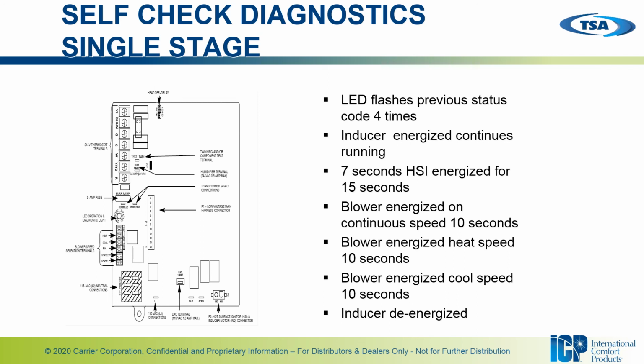So one of the changes on the control boards is that you now have a continuous fan speed. Okay, so that's the speed that it's going to function at when it goes into the blower self-test. Okay, then following that, it will energize the blower at heating speed for 10 seconds. And then following the heat speed, you're going to go into the cool speed for 10 seconds. All right, at which point your inducer will de-energize and you will complete the test.